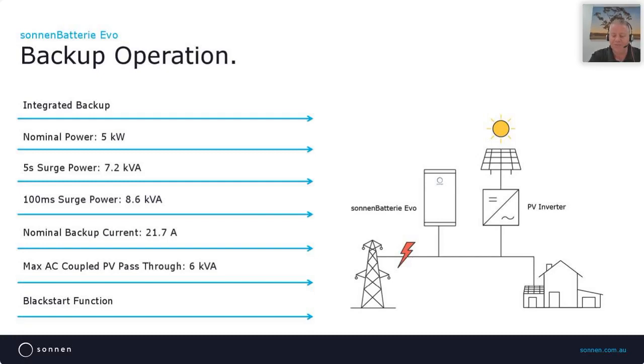The sonnenBatterie Evo has an integrated EPS backup functionality. This means no additional connections box or Sonnen Protect unit is required with this model, making for an easier installation. The backup supply is 5 kilowatt continuous and a nominal current of 21.7 amps. It has a surge capacity for 5 seconds at 7.2 kVA and a 100 millisecond surge of 8.6 kVA, allowing for startup voltages for separate devices in the home.